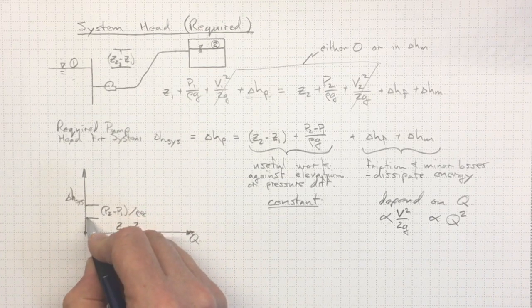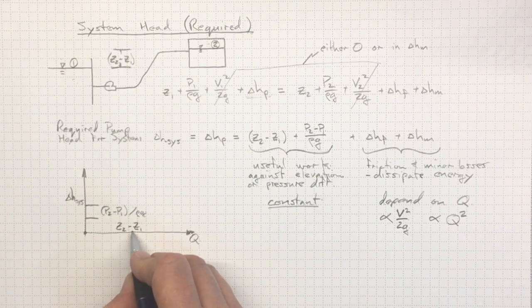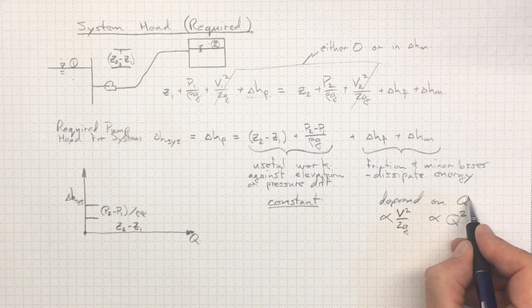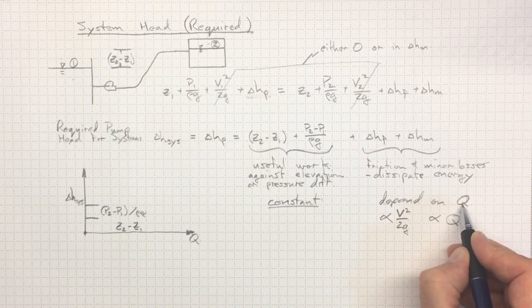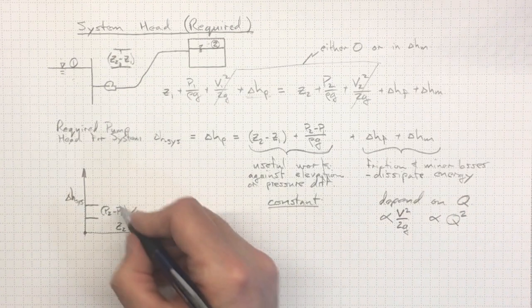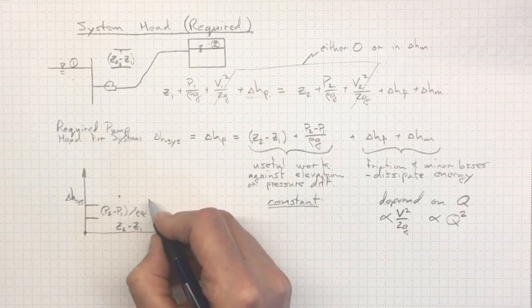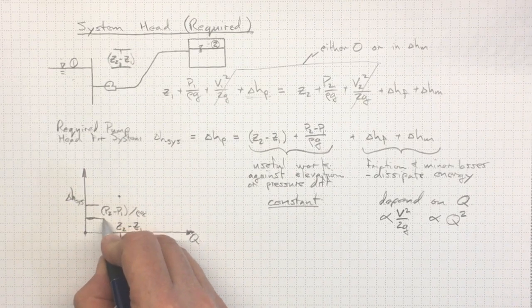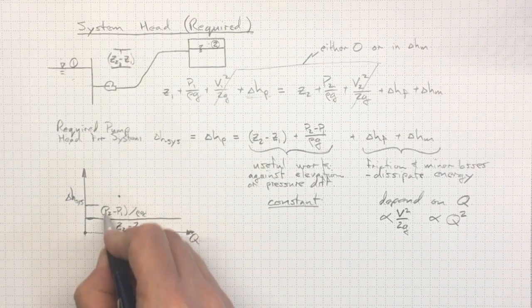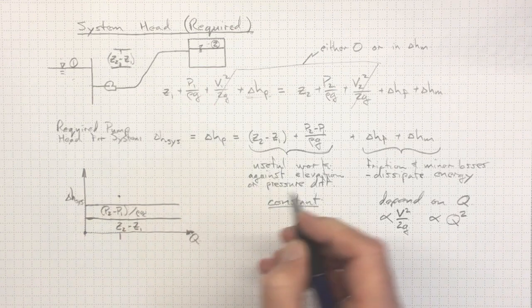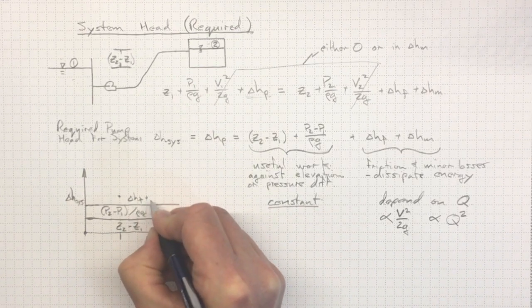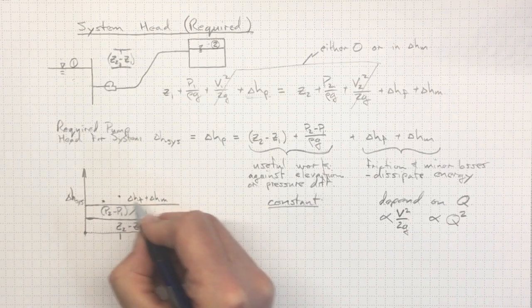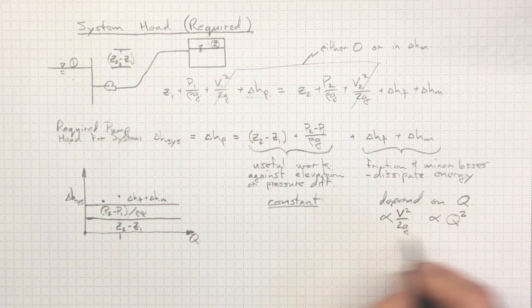If we don't have that much head rise across the pump, then there will be no flow. Now, if we have, in addition, some flow, there will be losses due to friction and minor losses. So, let's say we're up to here now at this flow rate. We've got an elevation difference, a pressure difference, and we've also got delta HF plus delta HM. It will be lower at low flow rates and it will go up as the square of the flow rate.